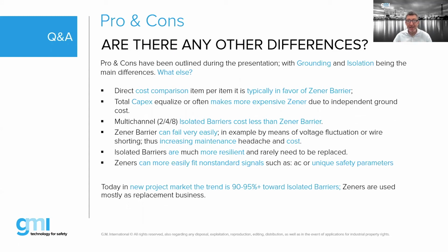We were just discussing this yesterday with a customer. I said, okay, if you use dual channel, you actually have 6 millimeters per channel, so it's a lot less dense than a Zener barrier. He says, okay, but if I drop one channel, I drop both channels. I said, no, they're independent. But in case of replacement, you have to disconnect 2 channels instead of a single channel. I find it quite an interesting discussion, because we're interfacing with PLCs, which have 32 channel DI cards, but anyhow.